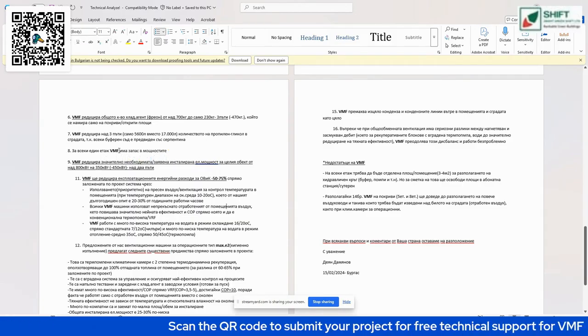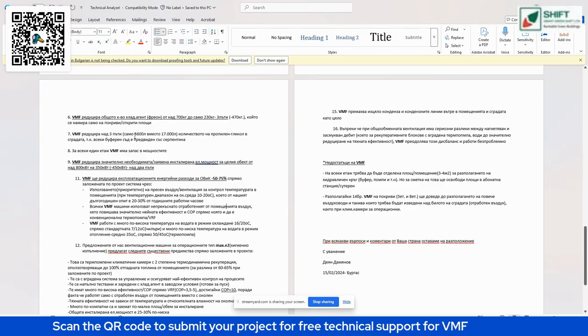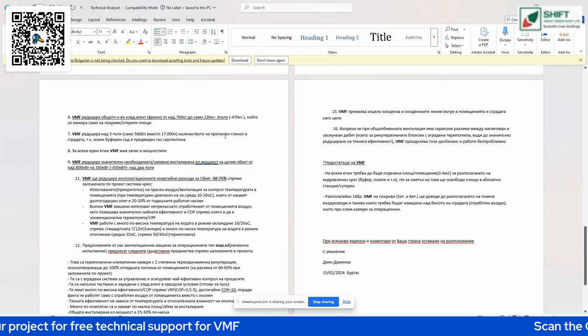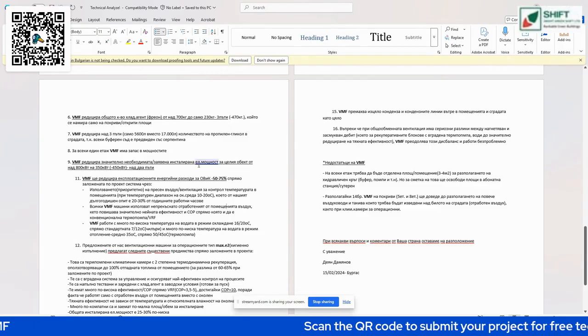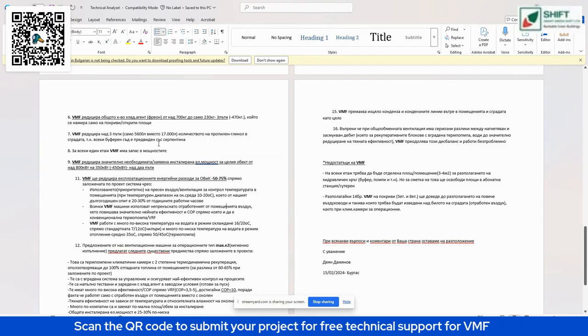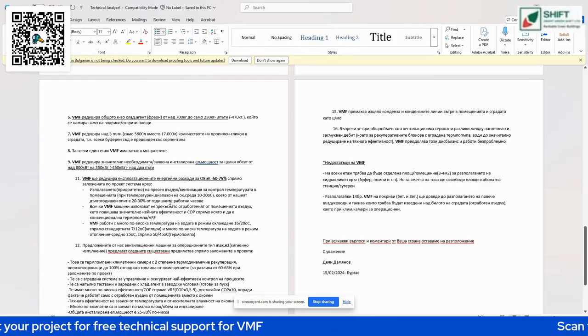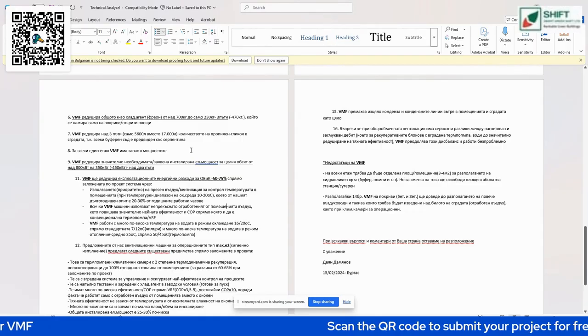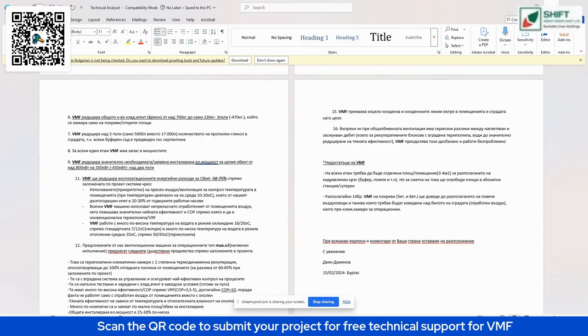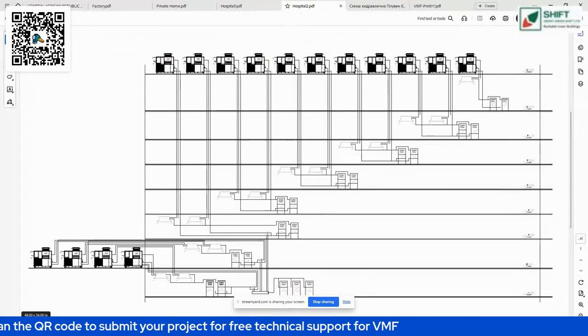Also in the original design, it's a water system, so we reduced more than 3 times the quantity of propylene glycol for the whole project. So the bigger the project is, the bigger the numbers are, and as you can see, the difference is still very big, 2 to 3 times in terms of installed electric power and refrigerant quantity.